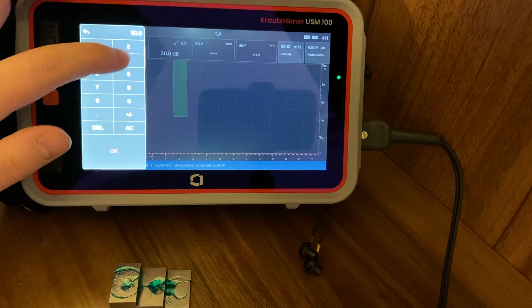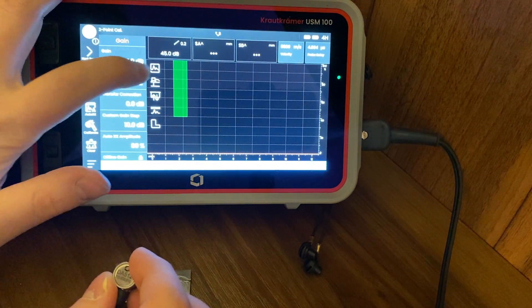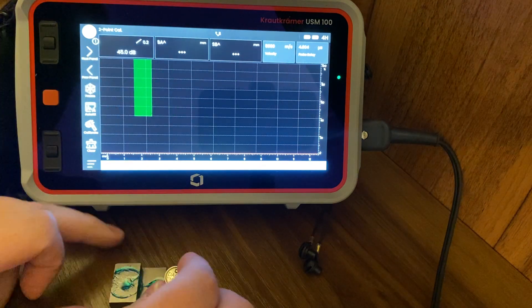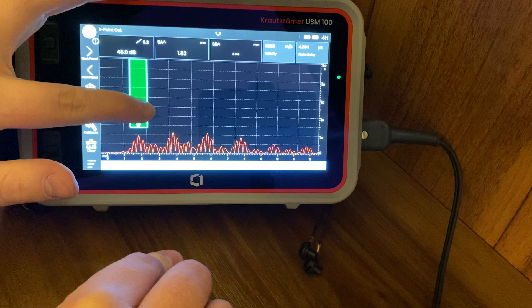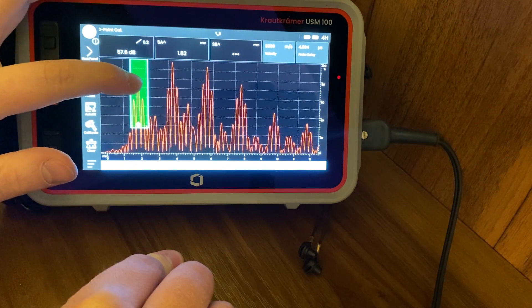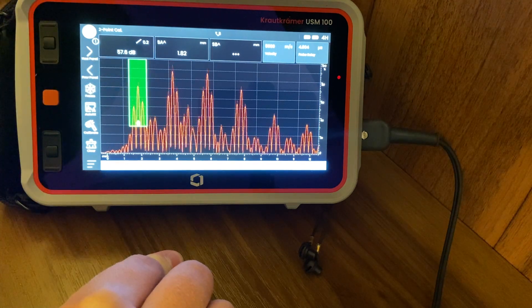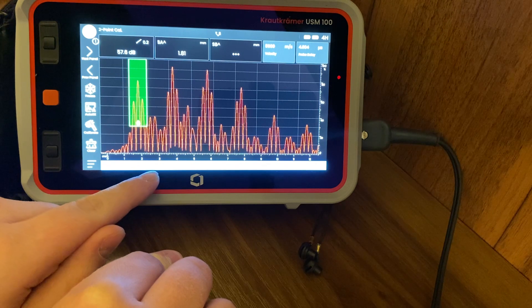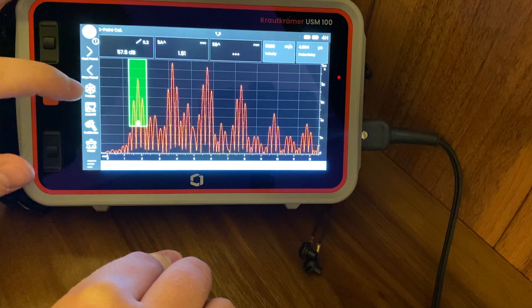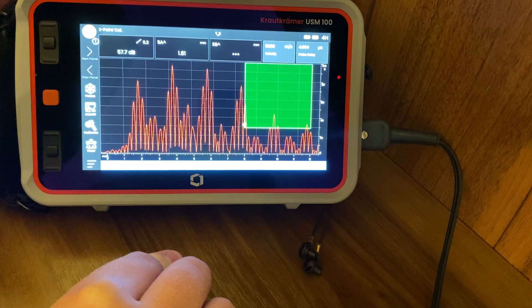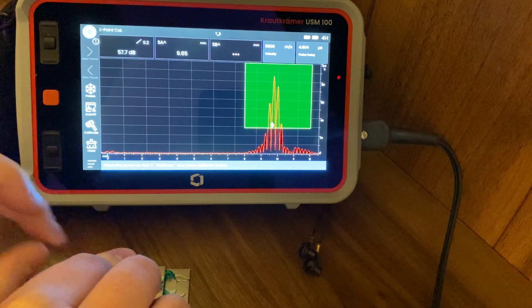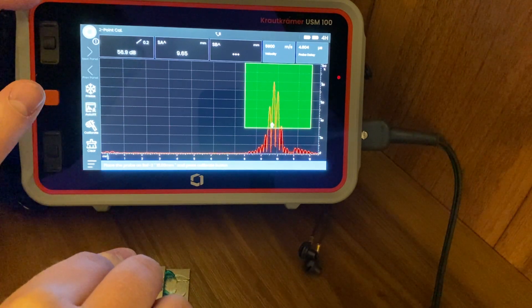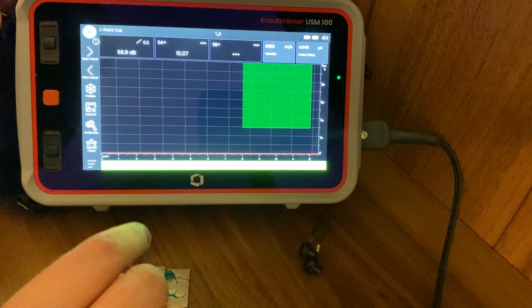Now to start off, it's going to increase the gain up to about 45 and we can play with it afterwards. Let's close it to make the screen a bit bigger. Obviously too small down here, so this little Auto XX feature increases the screen height to 80%. At the bottom, it tells you what to do - tells you to put the probe on reference 2 millimeter. You can't really see that on the screen unfortunately, but you can trust me. Auto XX, and then I say calibrate. Then we put it up on the 10 mil reference sample.